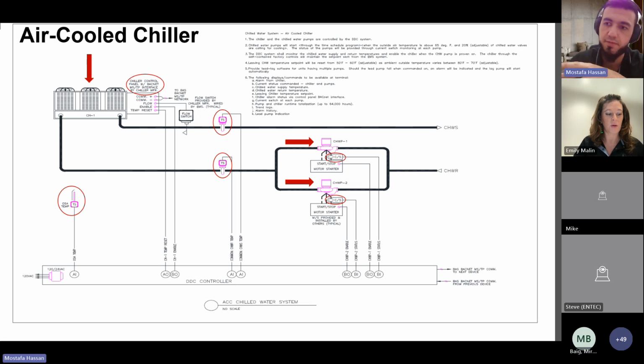Yeah, good question. Just based on my experience, because I don't really write tons of sequences, I think it's very efficient to do it through the VFD for one reason: when you run that wire, you're running an 18/8, right? Two for AC, two for power, two for turning on the pump, right? So you've got four points. You have fault, turning on the pump, controlling the pump speed.